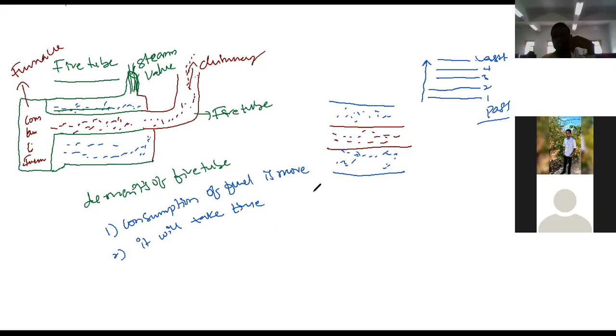It will consume a lot of fuel. That is the first thing. The second one is it will take a lot of time to convert water into steam. If that is the case, it can't produce a lot of steam. For example, to produce 100 kg it takes 5 to 6 hours. If an industry application requires 1000 to 2000 kgs per day, it will take a lot of time. So time is also one constraint in the fire tube boiler. So we are not at all recommending fire tube boilers for power plants. We are using water tube boilers. This is about the fire tube, and next I will explain what is called a water tube.